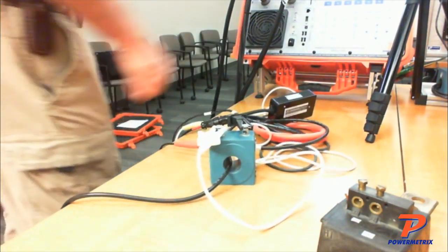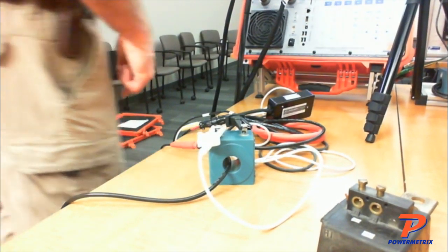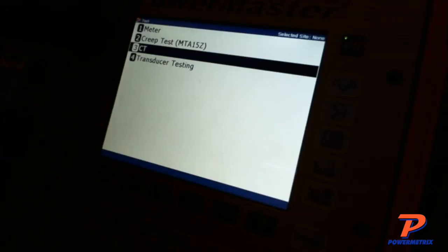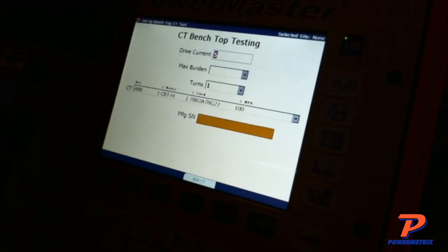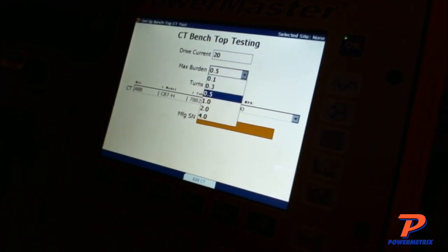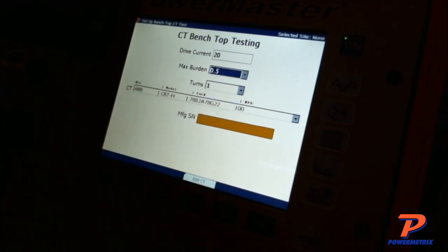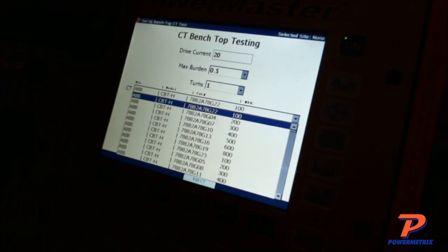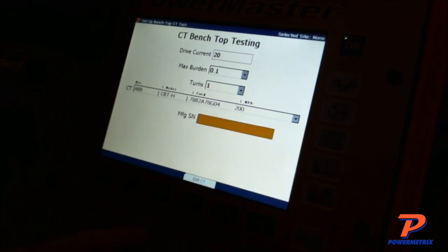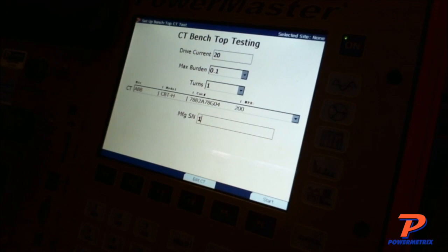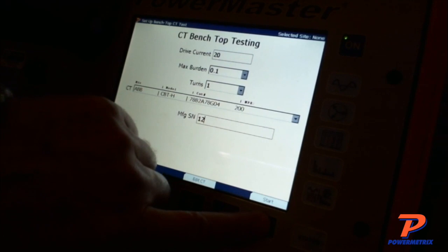All right, so let's do component test again, CT. And I'm going to run 20 amps again. Burden will go to 0.5 again, and I'm one turn. If I wanted to put 2 turns through there, I could, but I only put 1 turn because that should be high enough. We're going to go here, go at 200, and I'll just make that 1. 1, 2. Cool. Okay, now we will hit start test.